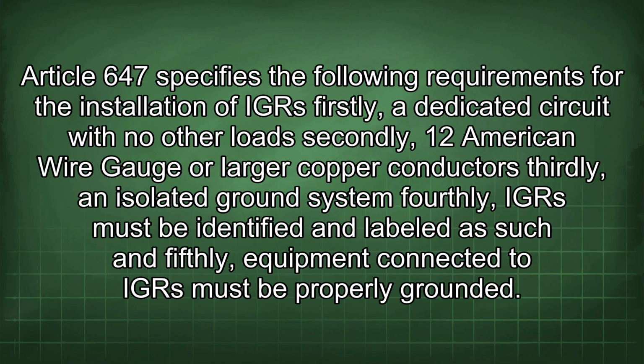Article 647 specifies the following requirements for the installation of IGRs. Firstly, a dedicated circuit with no other loads. Secondly, 12 American wire gauge or larger copper conductors. Thirdly, an isolated ground system. Fourthly, IGRs must be identified and labeled as such, and fifthly, equipment connected to IGRs must be properly grounded.